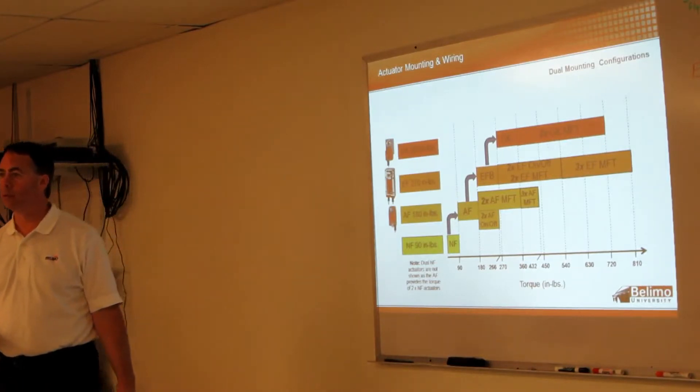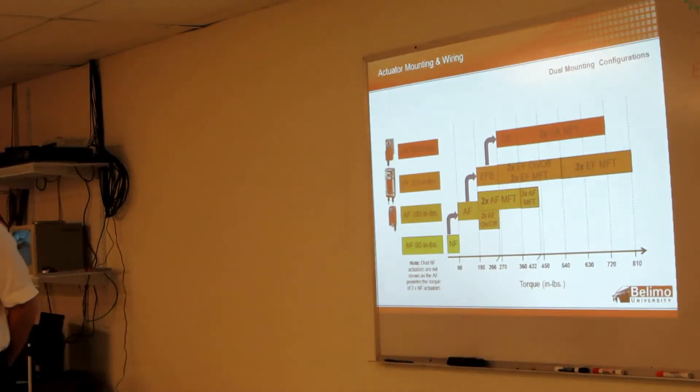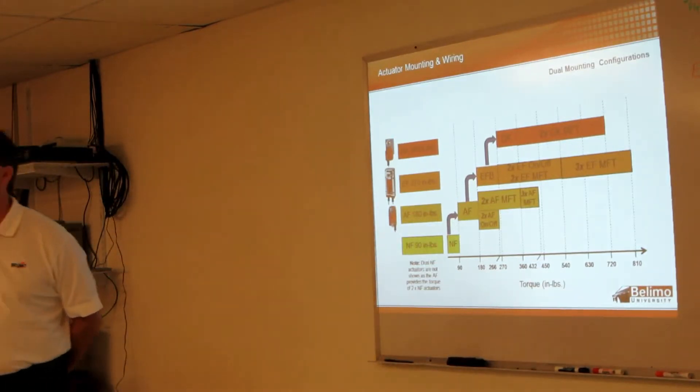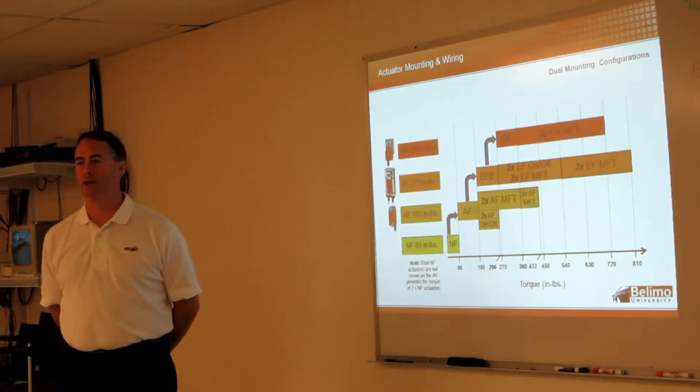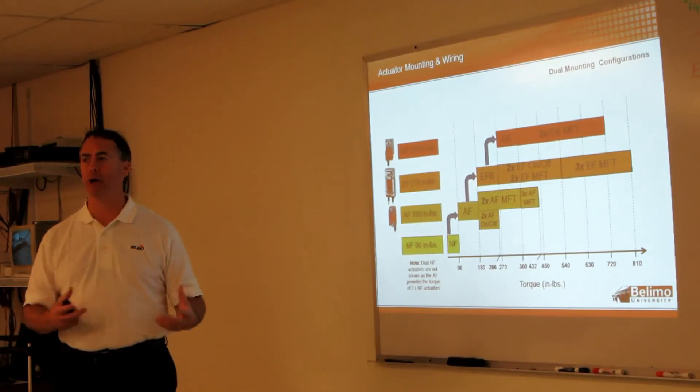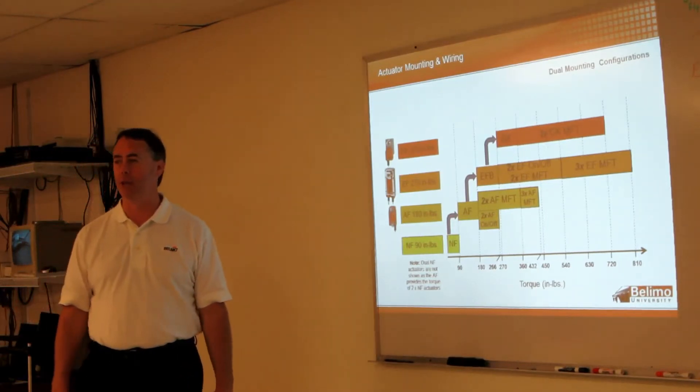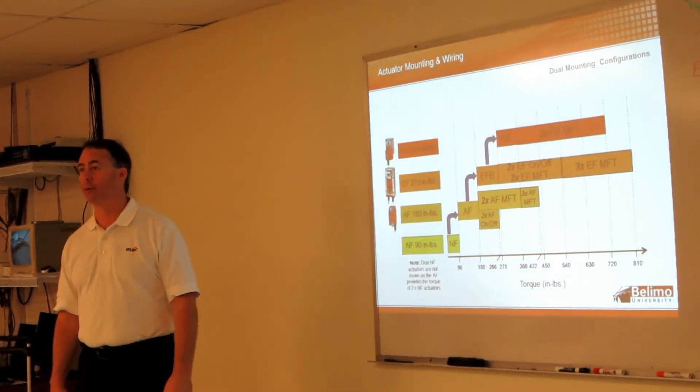Question? Well, if you already have a 90 in there and you're adding to that, I mean, is it just better off again just to replace it with the one you need? Yeah. I would rather than try to match up a new actuator and old actuator, you're better off just getting the new higher torque actuator. Yeah.